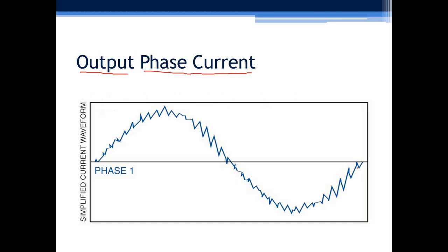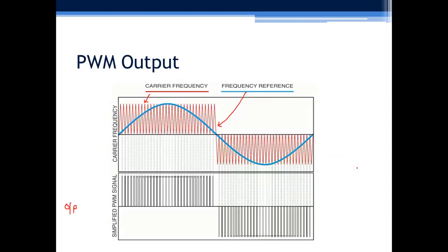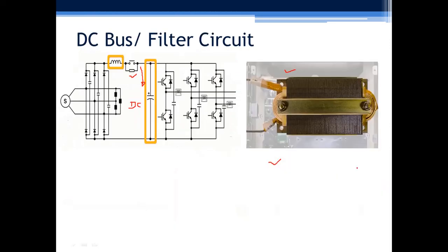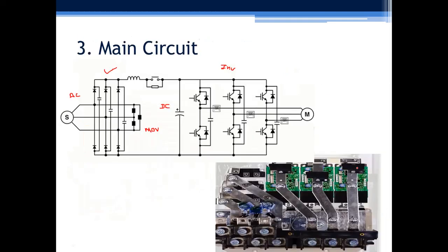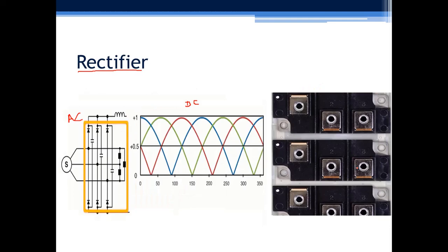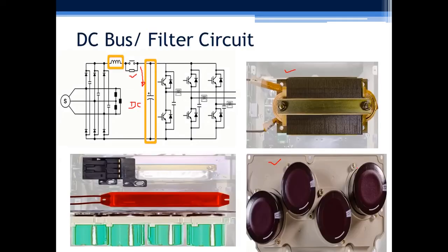So we have learned about the 3-phase induction motor drive. We simply understood different parts of the 3-phase induction motor drive. The first part is the rectifier, which converts AC voltage into DC voltage. Then the DC voltage is converted into variable voltage and frequency using VFD control. For this we make use of IGBTs, and using the control card we can set the required parameters. All IGBTs are switched on at very high frequency so that we get the required phase voltages.